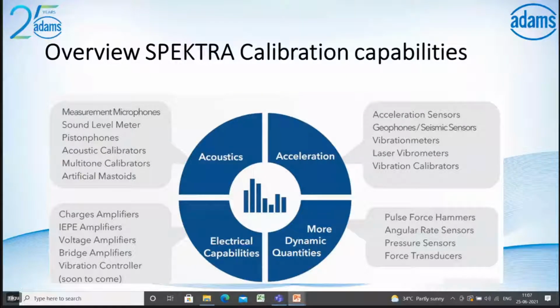For acoustics, the microphones that can be calibrated are measurement microphones and sound level meters, pistonphones, acoustic calibrators and artificial mastoids. For the electrical capability, it's a comparison calibration method for charge and voltage amplifiers, and for dynamic sensor calibration, such as angular rate sensors, pressure sensors, pulse force hammers and force transducers.